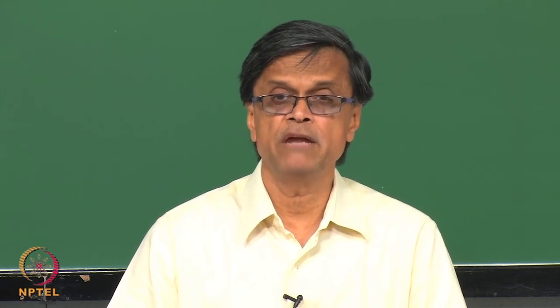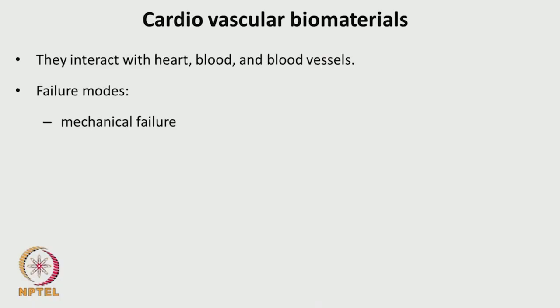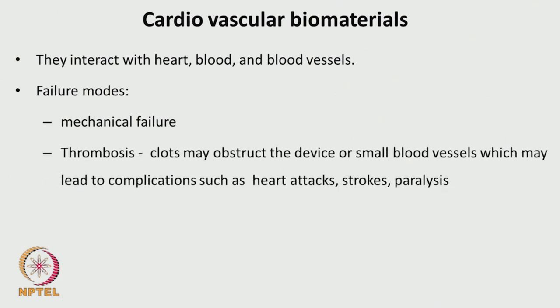We will briefly touch upon the metals, the ceramics, the polymers used in this area. Cardiovascular devices interact with the heart, blood and blood vessels, so they have different functions. The failure modes could be mechanical failure — for example, if you have the left ventricle assist device or a diaphragm valve which opens and closes, or a heart pump, they can have mechanical failure.